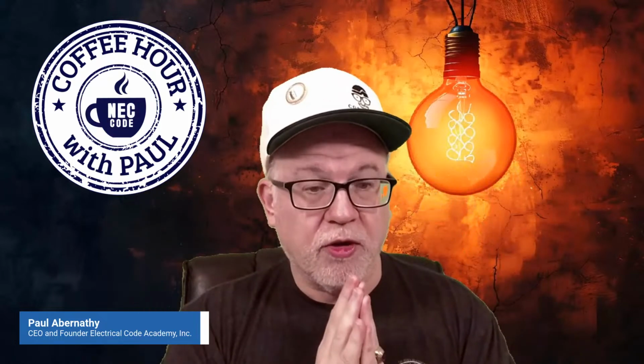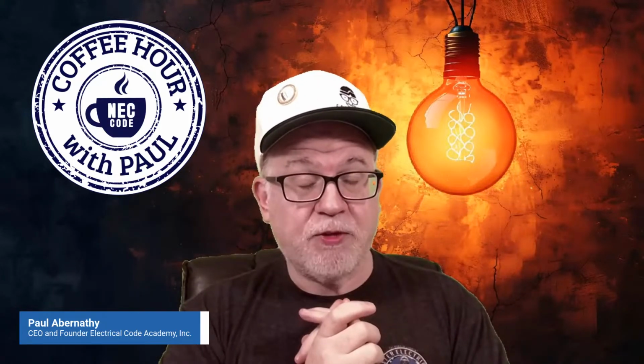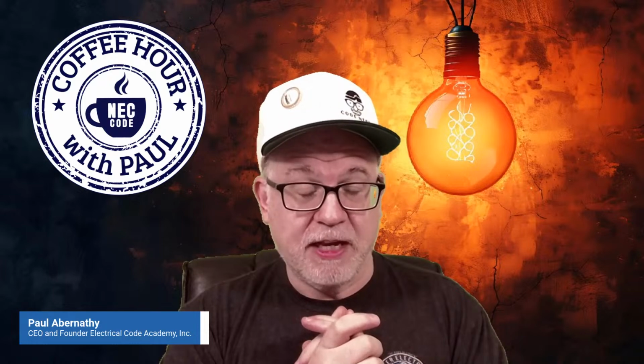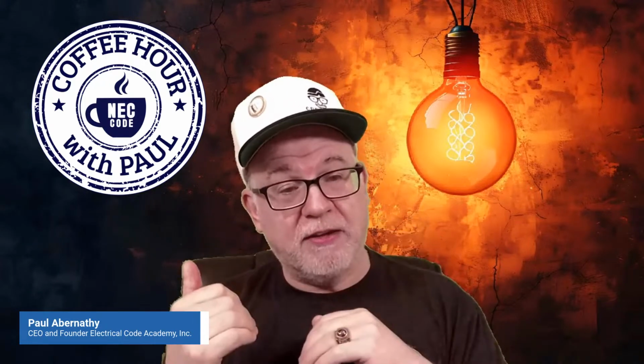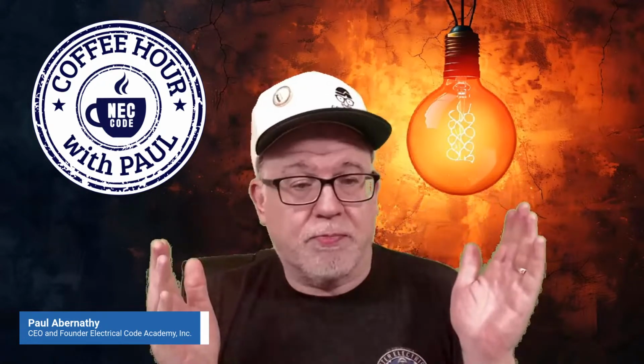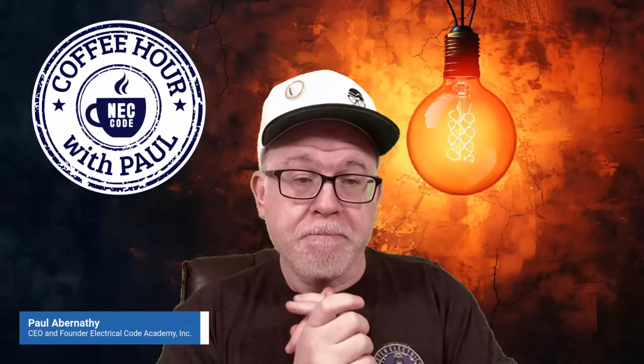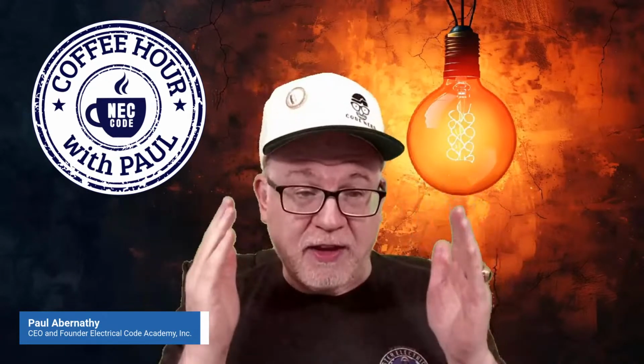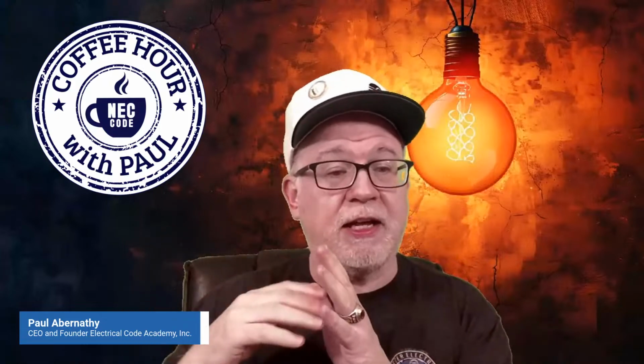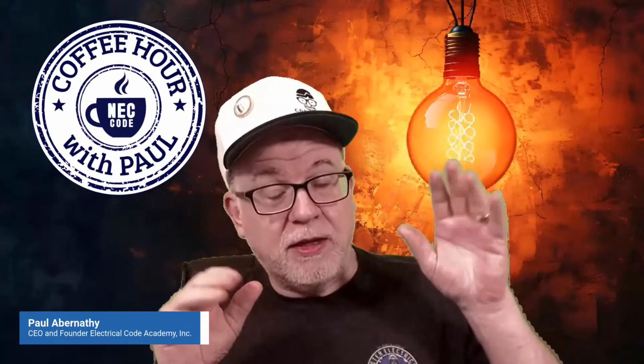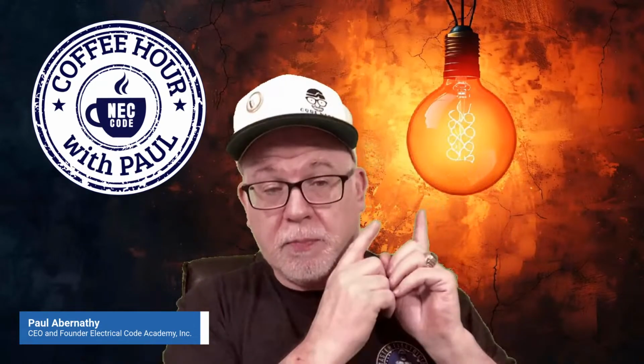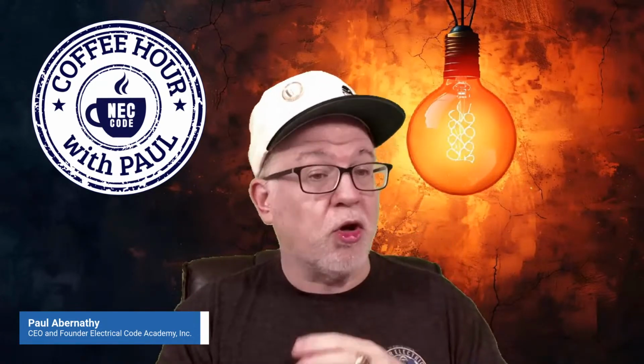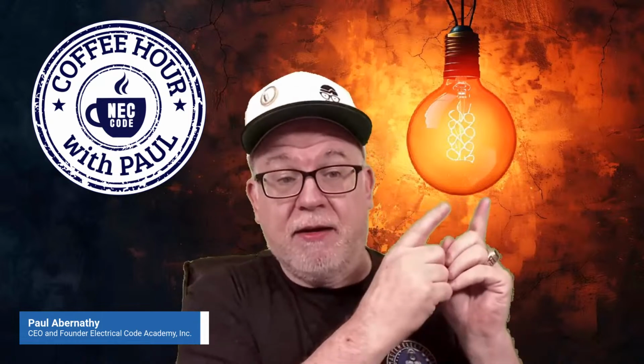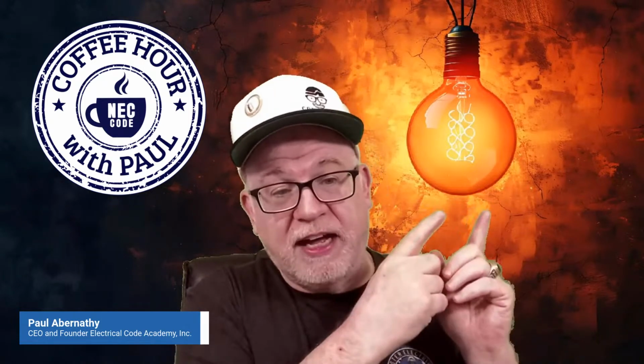I gave you a lot of things to think about. So what I want to do is give you a verbal mental picture synopsis, okay? Primary, wrap this thing up. Ready? Transformers, primary. If you're following 450.3(B) and you're dealing with 1,000 volts or less and 9 amps or more transformers, which more than likely is what you're dealing with, if you have primary and secondary protection, if you have a panel that you're feeding into a breaker in the panel and the secondary, then you have primary and secondary protection. You can go up to 250% on the primary, okay? You don't have to, but you can. Most engineers will just go to 125.